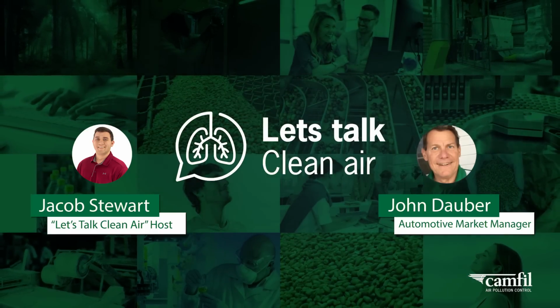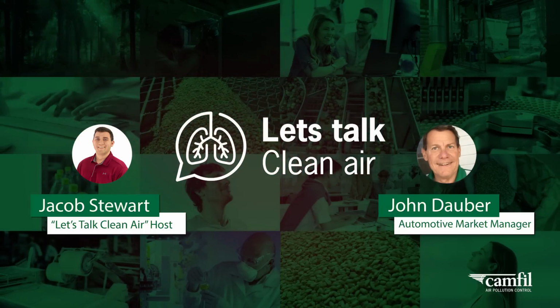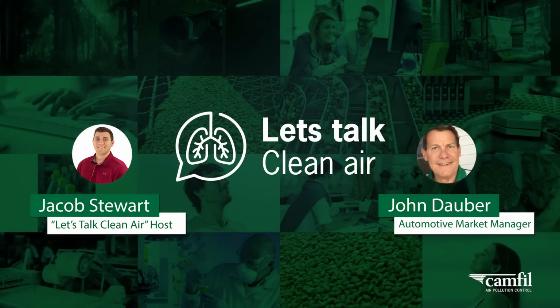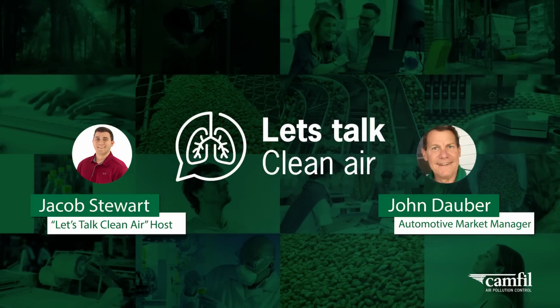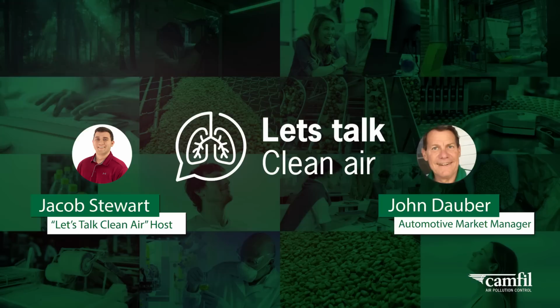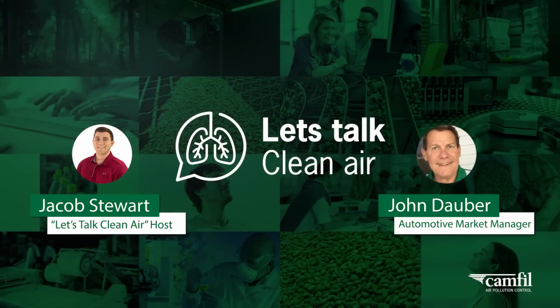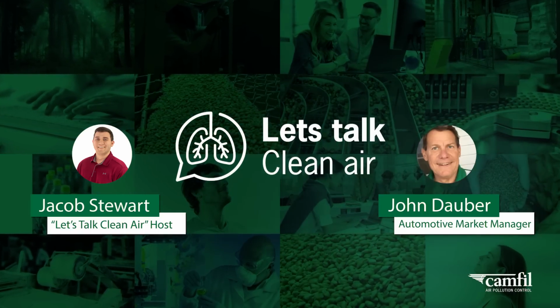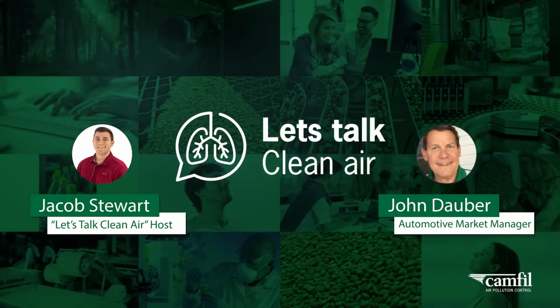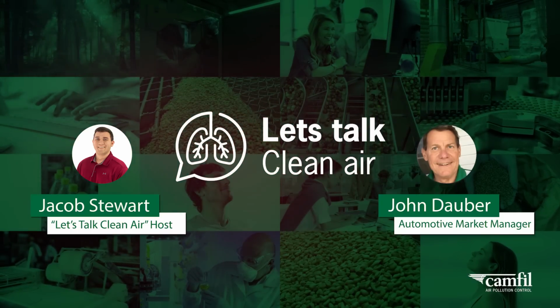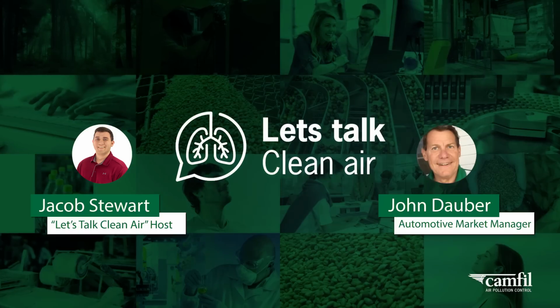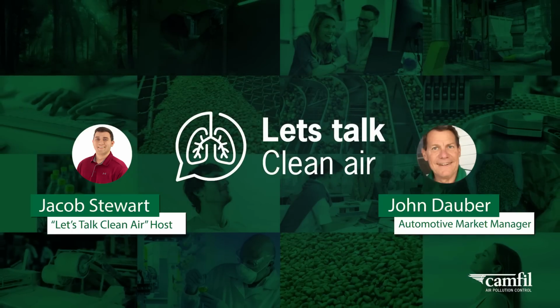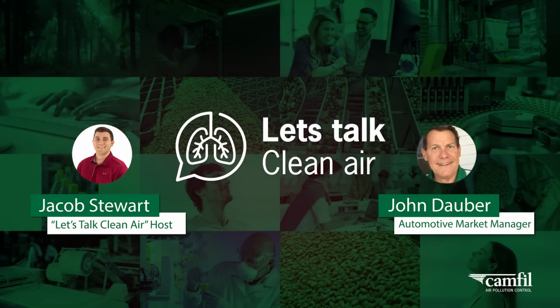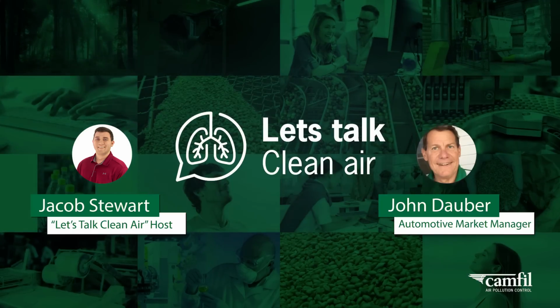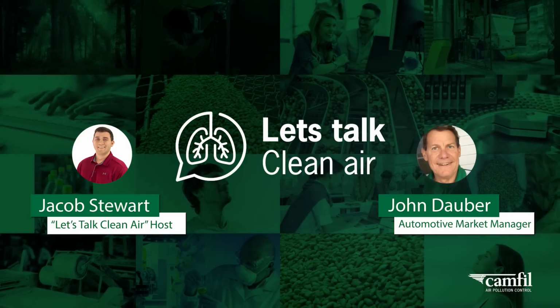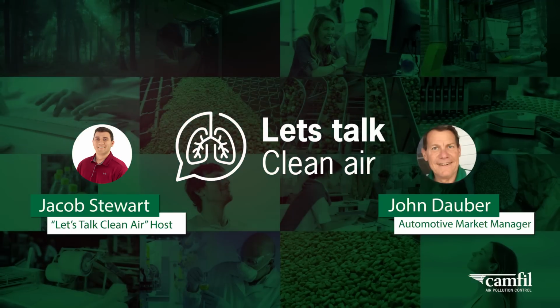And again, we've done performance-based testing on our collectors, on our media, on our stinger. Anything that we provide and build that we put on a dust collector has been performance-based tested. In other words, we've tested the collectors. I was actually at the site when we blew up a collector several times just to test the integrity of the collector, that it didn't come apart. It's pretty amazing if you've ever been around it, to actually know what's going to happen and see it. And it just changed my whole attitude about what can really happen with just a little bit of dust if there is an explosion in that dust collector. So we're very concerned about that.